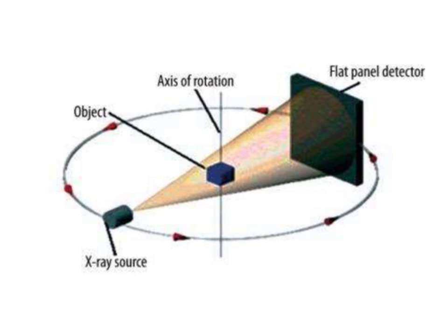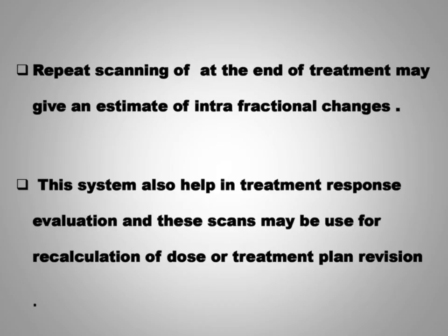But if the megavoltage beam is utilized for imaging with the help of an EPID, the problem is lesser contrast images, which we cannot define very clearly, so visualization is a problem, and there is more distortion from metallic implants and artifacts are produced, like dental implants in head and neck cancer, or hip prosthesis in pelvic tumor, which are commonly seen with megavoltage imaging.